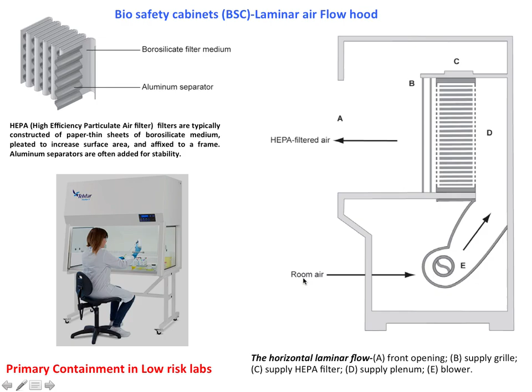So here you can see the primary containment in a low risk lab. Here there is no specific laminar hood. This type of laminar hood you can find in our cell and molecular biology lab also. This horizontal laminar flow hood consists of A, the front opening, B, the supply grill, C, the HEPA filter, D, the supply plenum, and E, the blower. So here the air blows in this way, and it is filtered by the HEPA filter, and only purified air comes in this way, and the continuous airflow is necessary to avoid any contamination inside the laminar flow.